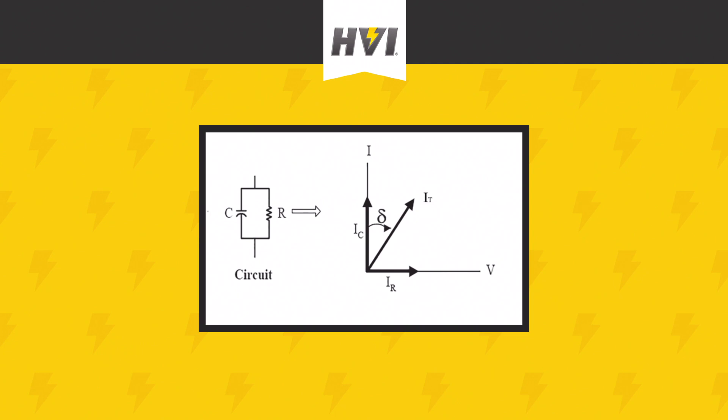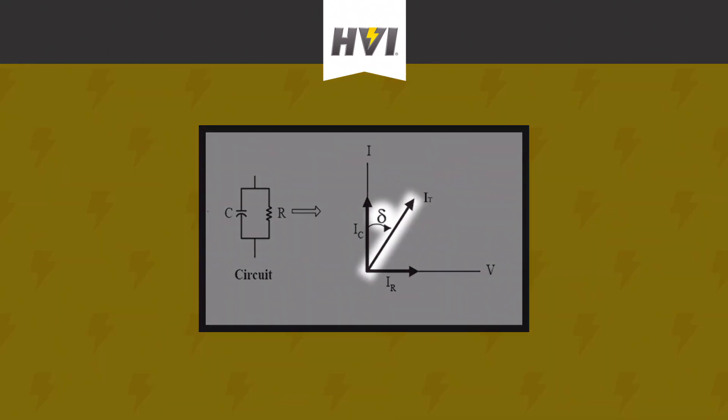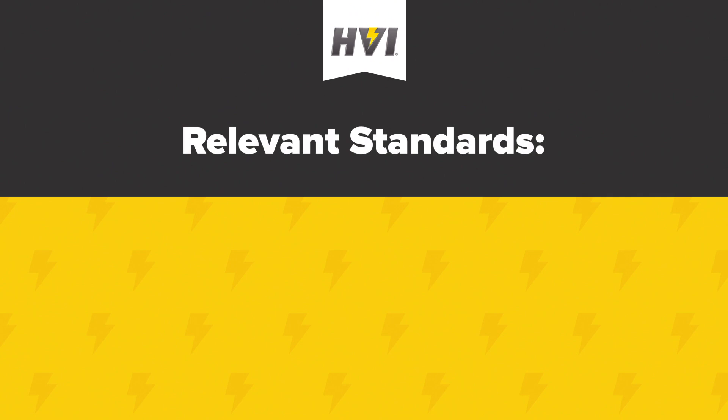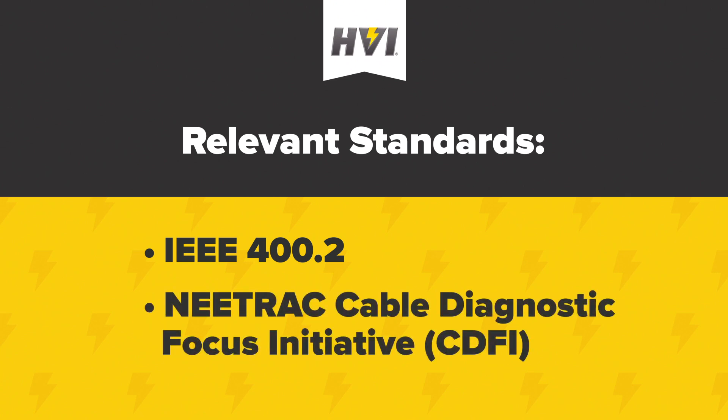Because the cable no longer acts as a perfect capacitor, the phase shift between voltage and current will be something less than 90 degrees. The extent to which the phase shift is less than 90 degrees indicates the level of insulation degradation. This loss angle is what's measured and analyzed in Tan-Delta testing. Results of the test can be interpreted according to relevant standards in the IEEE 400.2 standard for VLF testing of cable systems, as well as those provided by NEETRAC's Cable Diagnostic Focus Initiative or CDFI.